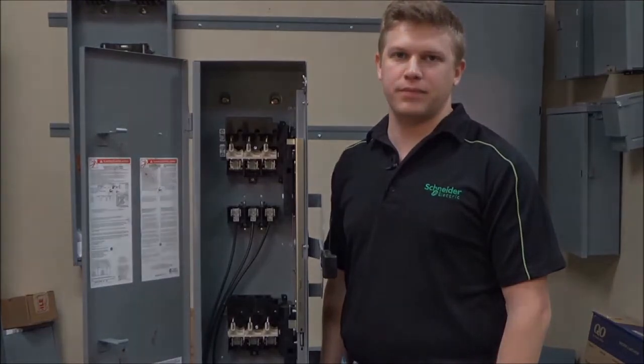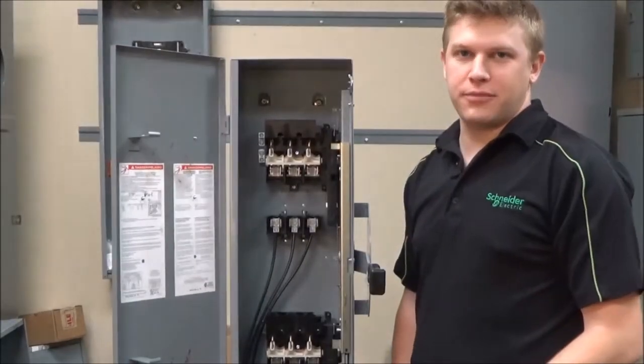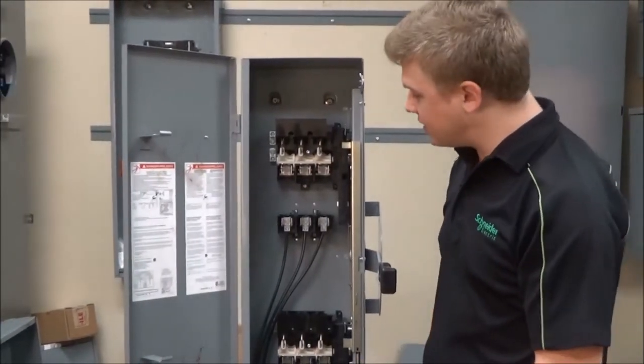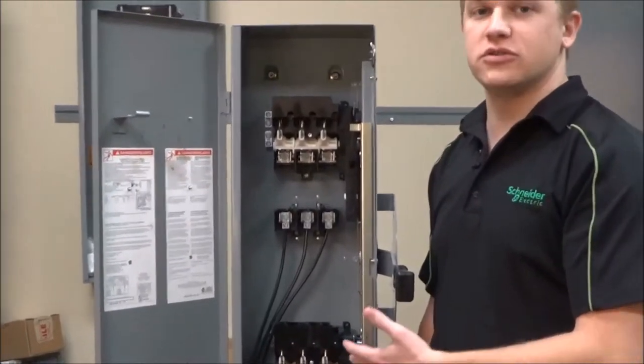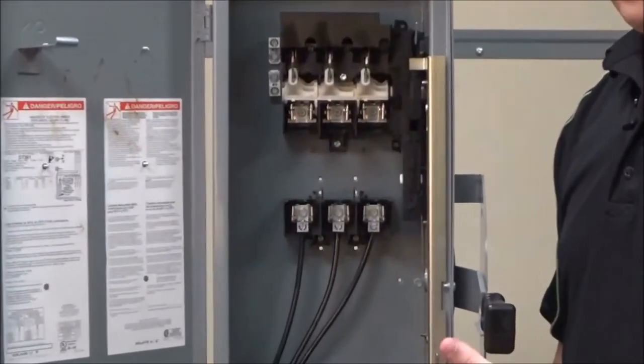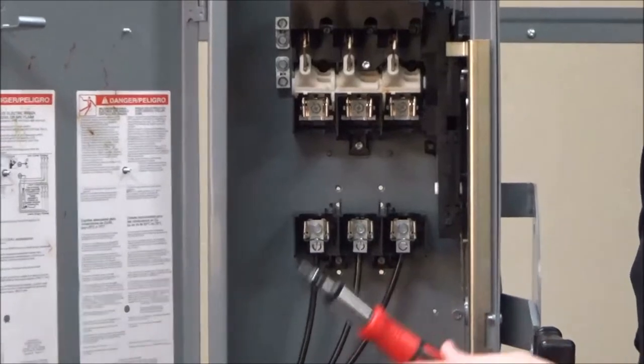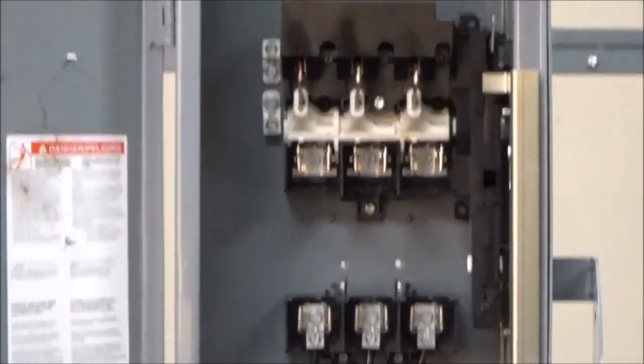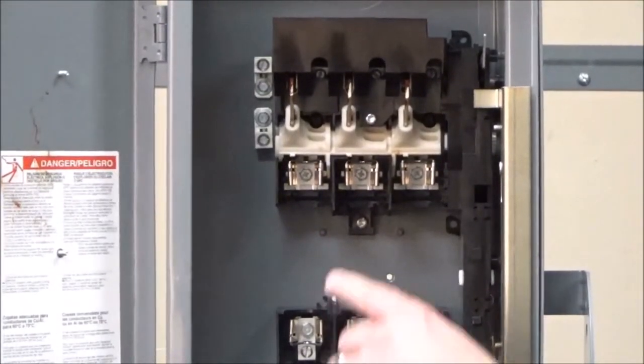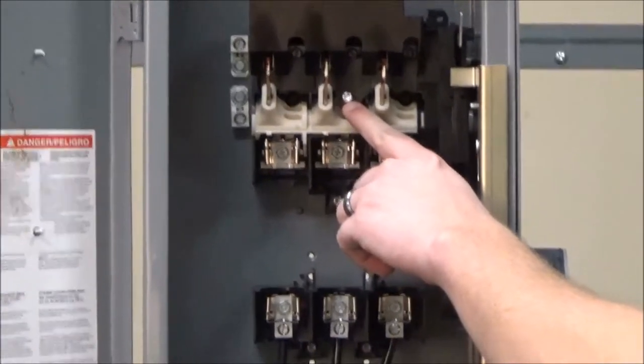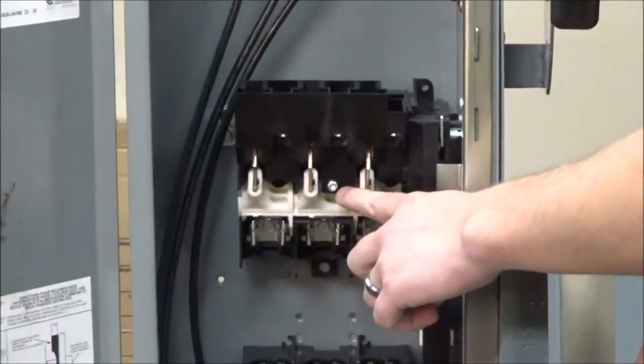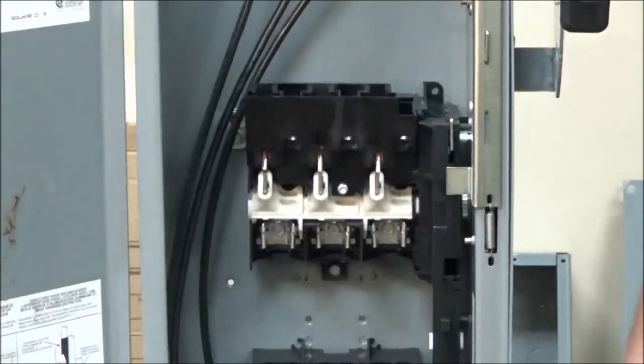The first step, if your switch already has the fuses installed, would be to remove the fuses. Then using a Torx screwdriver, you would remove the arc shields by removing this screw and this screw, and retaining the arc shields.